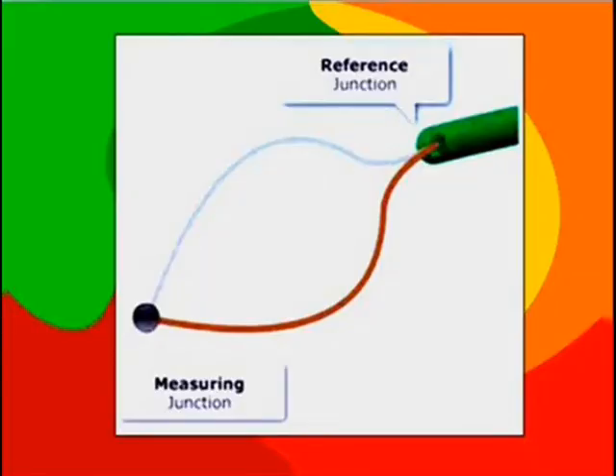Let's look at this picture. Okay, you can see which part is the reference junction and which part is the measuring junction. When there is a temperature difference between the measuring junction and the reference junction, a tiny electrical current flows. When the voltage is measured at the reference junction, the temperature at the measuring junction can be deduced. The relationship between temperature and voltage is a positive one. Increase in temperature produces increase in voltage. Decrease in temperature produces decrease in voltage.